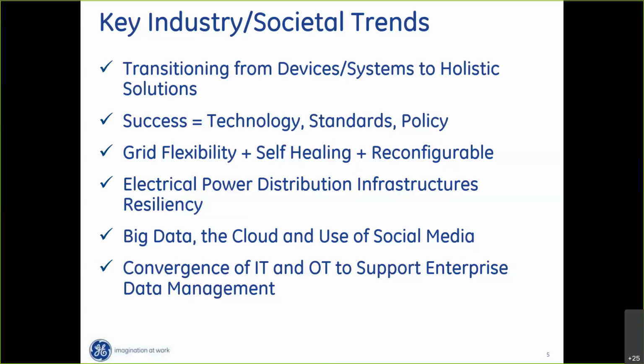The intelligent electronic device, the microprocessor-based device, has two-way communications. So we look for opportunities to have that as a node in a network. The relay has value to the utility, but when that relay is used in a substation automation system, or a special protection scheme, or some greater integrated solution, that solution has much more value to the utility. So devices and systems are good, but the holistic solution is what we really want to strive for.